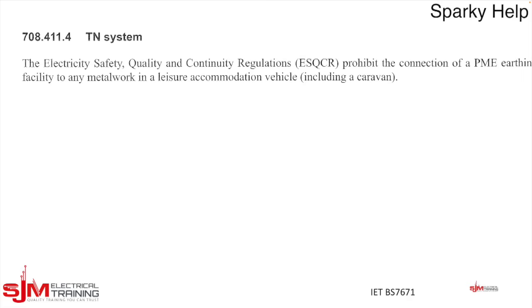What do our regs say about it? Well, these are from BS 7671, so we've got one there, 708. The Electricity Safety, Quality and Continuity Regulations prohibit the use of a PME facility in leisure accommodation vehicles, in a caravan. So caravan parks are not allowed to have a PME supply, and they would be connected from, let's say, a 16 amp socket like that. So we don't want them in. The Electricity Safety, Quality and Continuity Regulations are what the electricity company works to. That was formerly known as the supply regs, a bit easier to remember.